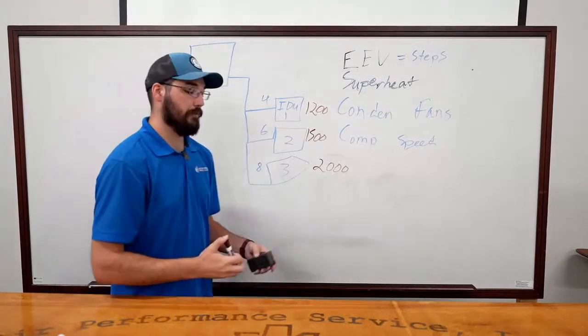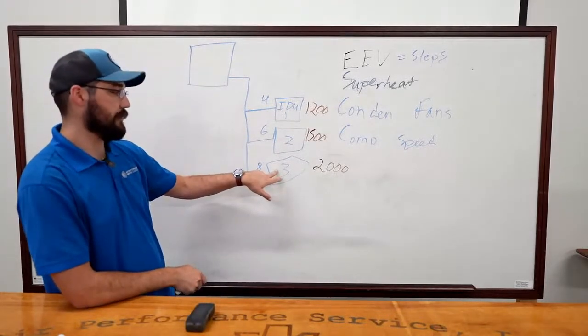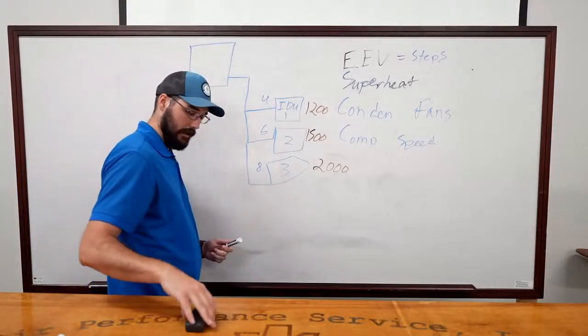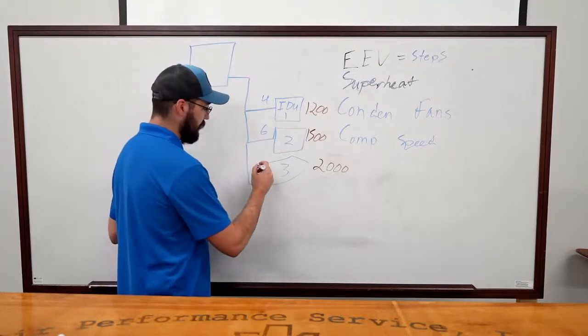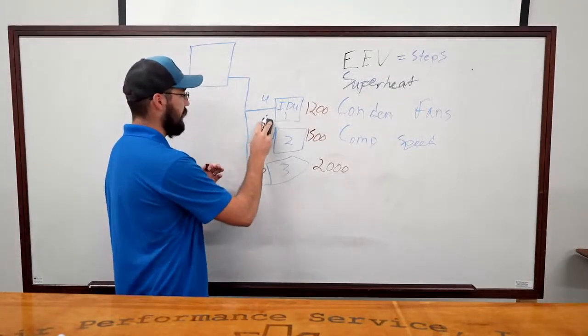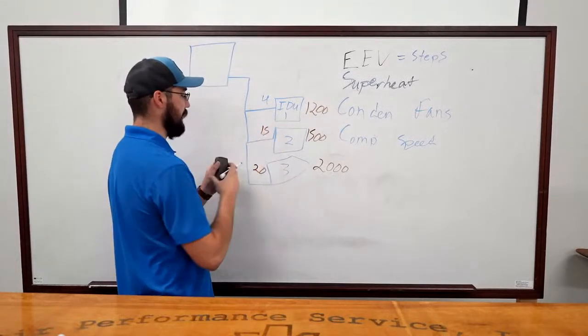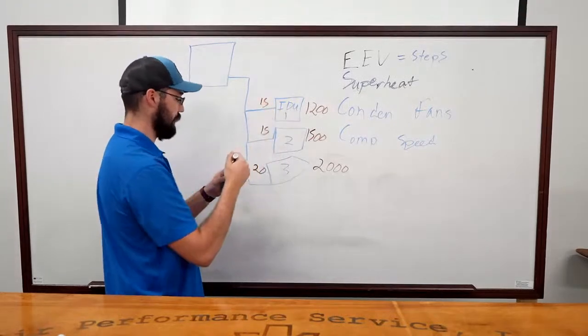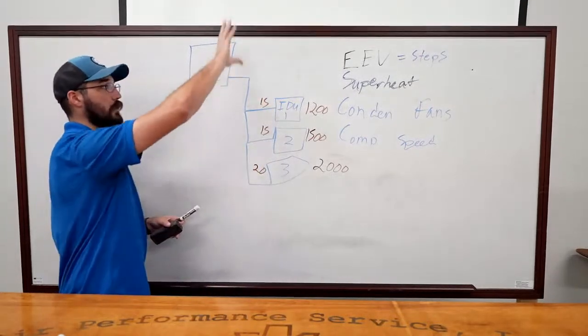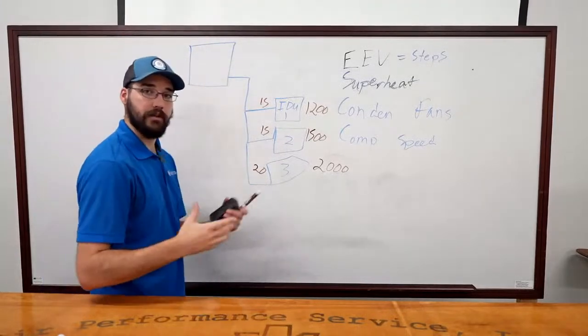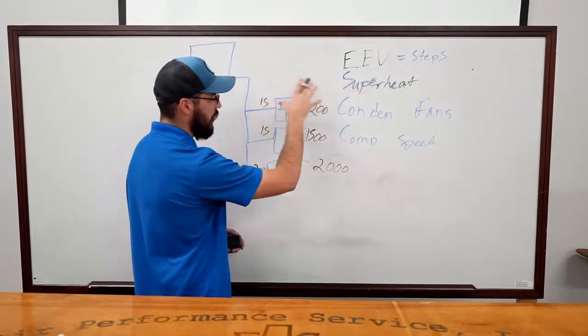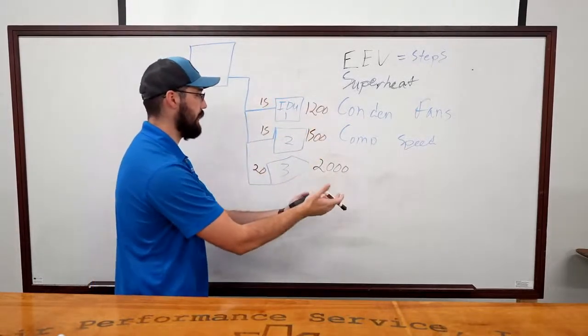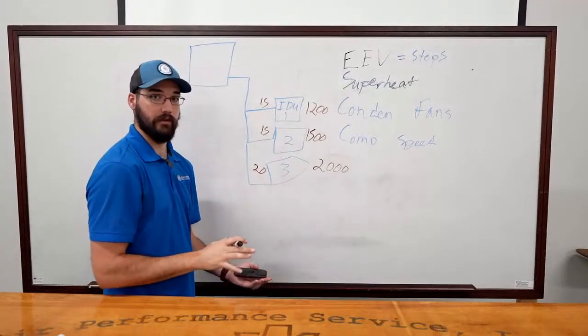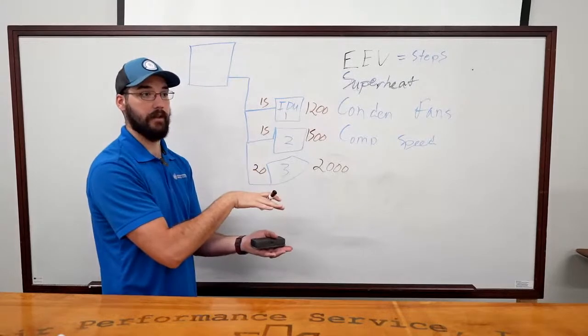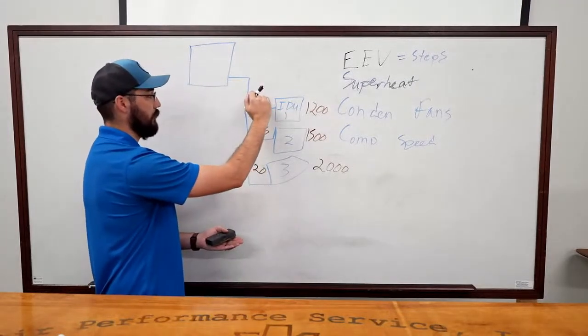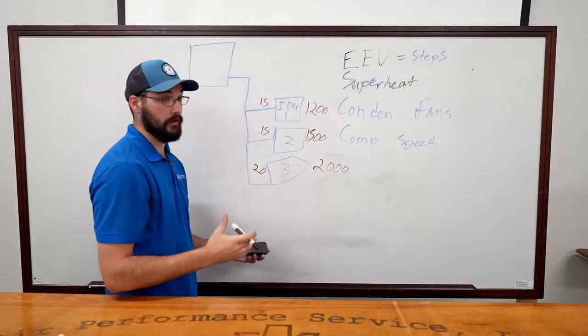You can even let it go a little further. The longer you let this thing run, you're going to see your discharge air temps don't come down. They're going to stay high, and your superheats are just going to continue to build as well. So this thing may be up to 20 degrees. This one may be sitting at 15 or higher. Say this one's at 15 as well. And it's struggling. Again, your compressors aren't ramping. Your condenser fans aren't having to ramp because your head pressure is not there. All of this combined gives you an indicator, because these are extremely high superheats for these systems. They run just a few degrees of superheat. That's what they're meant to do. So to get positive 10 degrees of superheat, something's wrong.